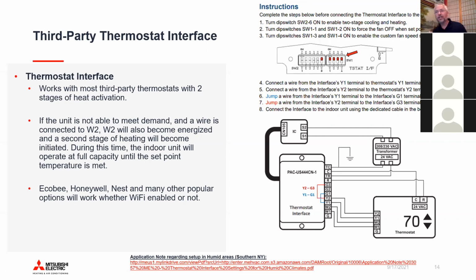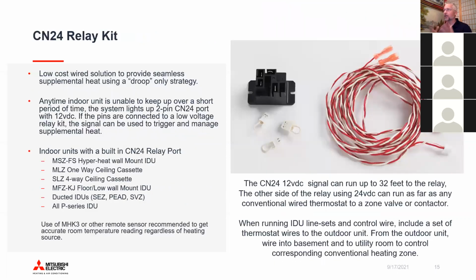That way there's not a big comfort threshold before it turns on. People won't even notice it, but you're going to continue to use the heat pump throughout the entire cycle and season. Okay, a little bit closer up picture of the CN24 relay kit. There's not much to this. The secret sauce is really that it's got plugs that fit directly onto the control panel of the indoor unit and go right to the CN24 port.